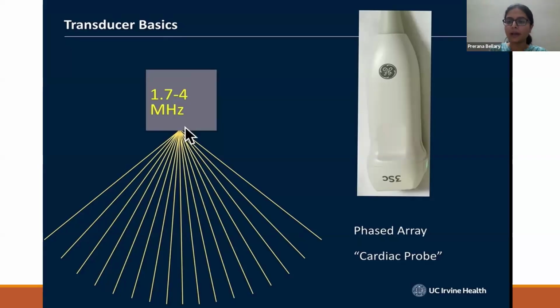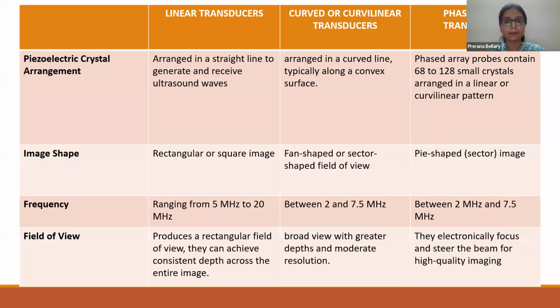Unlike the linear and the curvilinear probe, where all the sound waves are emitted at the same time, here they are emitted one after the other at a certain time period. Right, so that's why it appears in phases. That's why it is a phased array probe. So to put these three together, like I said, the piezo crystal arrangement in a linear and curvilinear probe would be in a line, either a straight line or a curved line, but in a phased array probe, it is in a grid. The image obtained will be rectangular in a linear transducer, fan-shaped in a curvilinear transducer, and sector-shaped in a cardiac probe. As for frequencies, the linear transducer is a high frequency probe, while curvilinear and phased array transducers are low frequency probes.